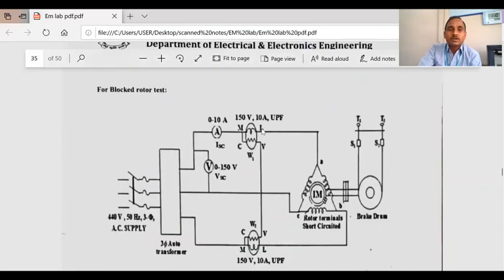Okay, so now for the blocked rotor test, we have to block the rotor by tightening the belt through T1 and T2, and again apply the voltage, which should not exceed 4.5 ampere of the induction motor. The 4.6 ampere is the full load rated current of the induction motor we are using in that laboratory. So depending upon your induction motor, calculate the full load current. That is given in the nameplate details also. Okay, so by observing that, we need to increase the voltage up to the current rating of the induction motor. Okay, so this is called the blocked rotor test.